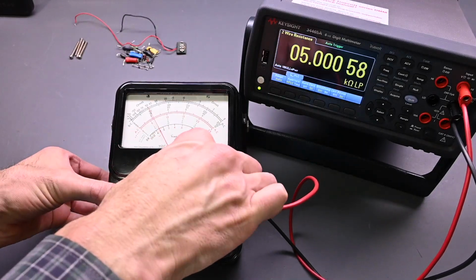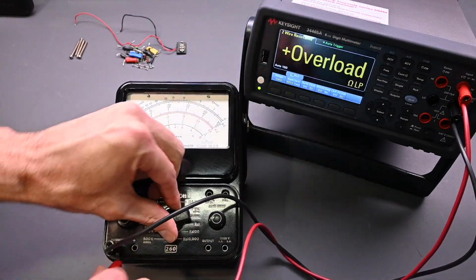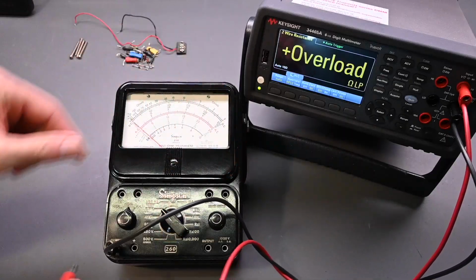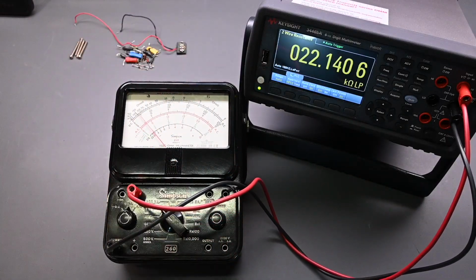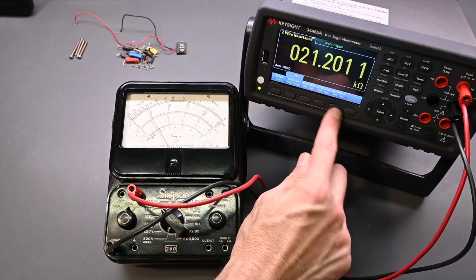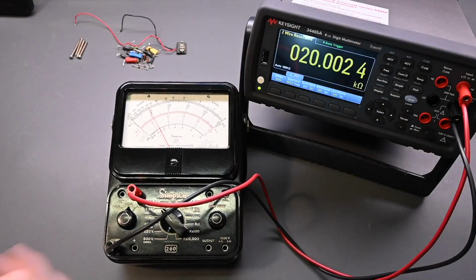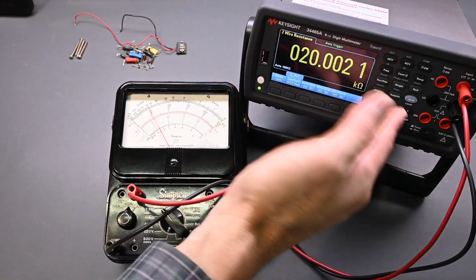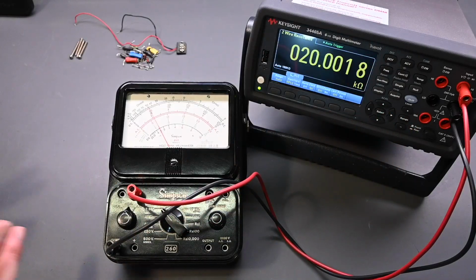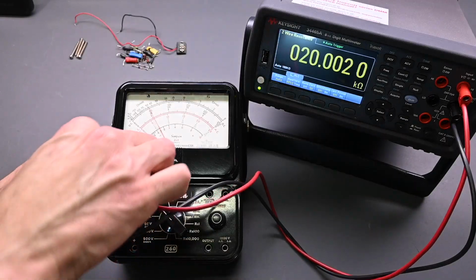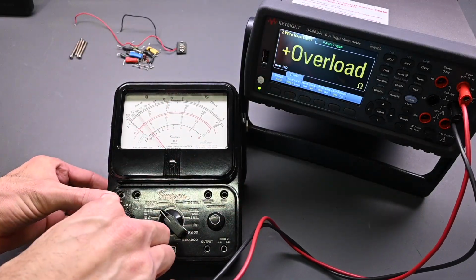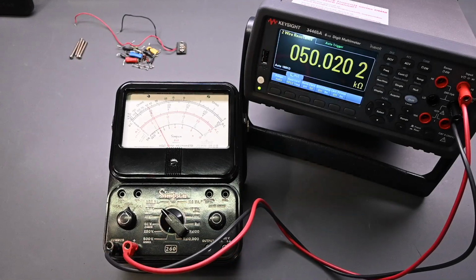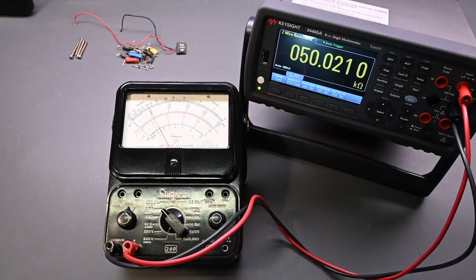All right, so now over here, and I'll just move this down to the 1 volt, and let's go right here. And this can actually change now to normal power rating. So this has 2 outputs, high and low power for the ohm meter function, so it's handy when you're measuring very sensitive circuits. So on the 1 volt input, 1 volt times 20,000, of course, is 20,000, and perfect, look at that, no problems there. So now move this down here to this terminal jack, and 50,000 ohms, perfect. That's what it should be.